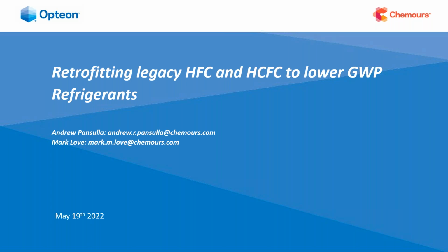Okay. Then one final one before I turn it over to Dale. Can you top off an existing 404A system with 449? Much like you shouldn't mix 448A and 449A, mixing refrigerants is not a recommended practice. So no, we would not recommend topping off a 404A piece of equipment with 449A. You would want to fully recover the 404A. I mean, 404A is the new refrigerant gold, if you will, anyway. Making sure you're reclaiming that 404A is really key to a good refrigerant management plan.